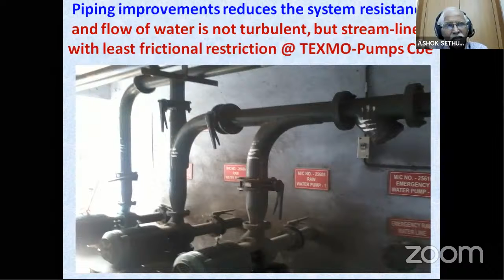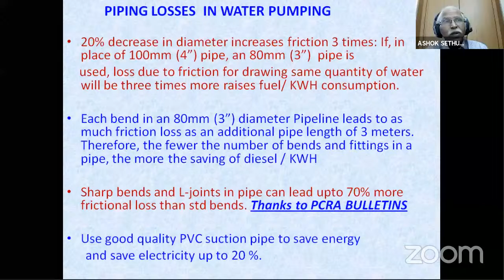By changing all the GI pipes to MS ERW pipes, electric resistance welded ERW pipes, they can achieve almost 20% in their pumping system energy consumption. Leave alone the pumps and pipings and the fittings. For the pipe fittings, instead of using sharp elbows and sharp bends, go for conjoined bends in the airlines and in the pumps. See in traffic, when you are driving your vehicle, you have to go slow into the bend and come out of the bend fast. This is what is deployed here also.